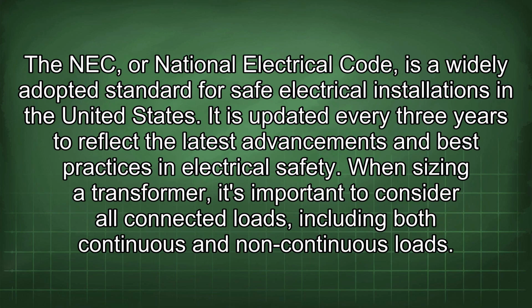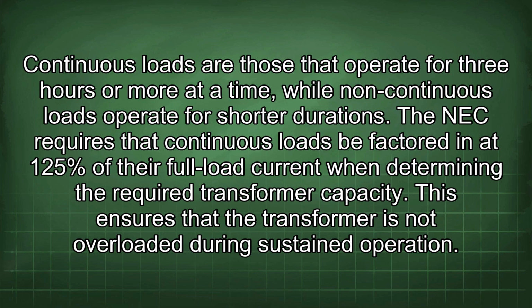The NEC, or National Electrical Code, is a widely adopted standard for safe electrical installations in the United States. It is updated every 3 years to reflect the latest advancements and best practices in electrical safety. When sizing a transformer, it's important to consider all connected loads, including both continuous and non-continuous loads. Continuous loads are those that operate for 3 hours or more at a time, while non-continuous loads operate for shorter durations. The NEC requires that continuous loads be factored in at 125% of their full load current when determining the required transformer capacity. This ensures that the transformer is not overloaded during sustained operation.